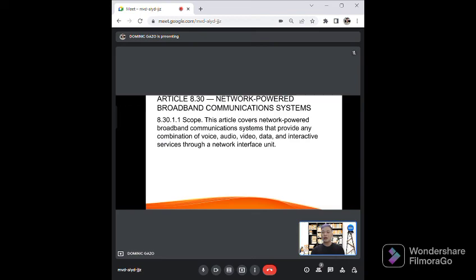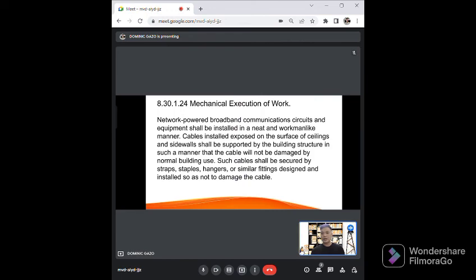For the scope, Article 830.1.1 scope. This article covers the network-powered broadband communication systems that provide any combination of voice, audio, video, data, and interactive services through network and interface unit. For Article 830.1.24, mechanical execution of work, this network-powered broadband communications shall be installed in a neat or workmanlike manner. Those cables installed on exposed surface ceilings or sidewalls shall be supported by structure in such a manner that the cable will not be damaged. And those cables shall be secured by straps, hangers, or similar fittings designed and installed so as not to damage the cable.